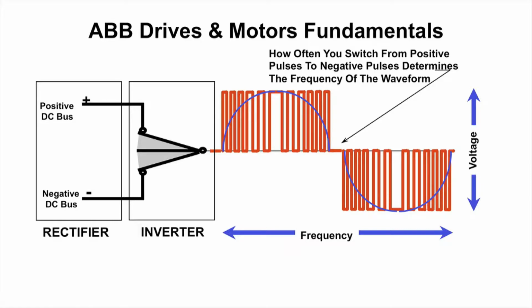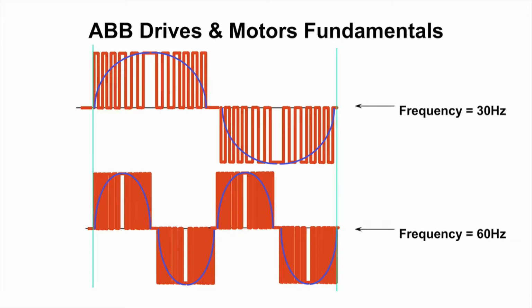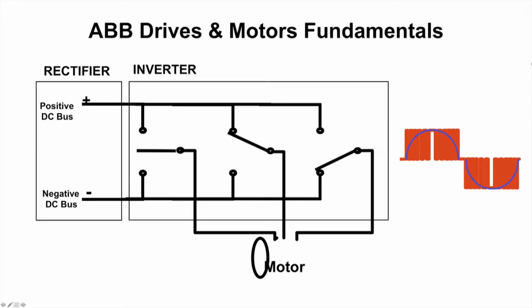So thousands of times a second, on again, off again, but it's how many times we transition from on to off that determines how fast the frequency is on this guy. So if you look, you'll see a 30 hertz or half speed signal. The pulses are widely spaced, but on a 60 hertz full speed signal, the pulses get closer together. So you get more on again, off again cycles in a second. So by varying that frequency, we then change the speed that the motor goes.